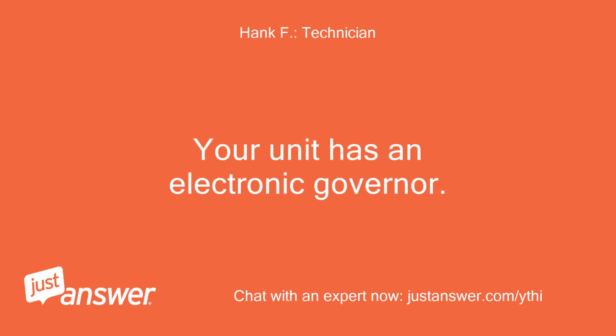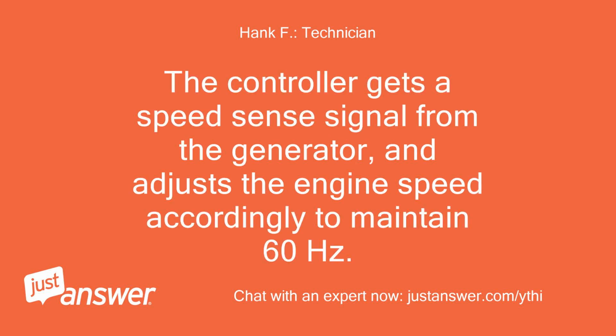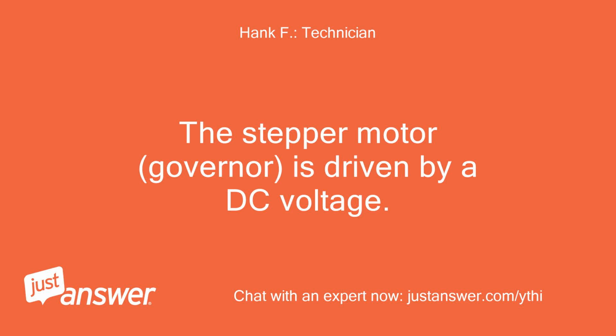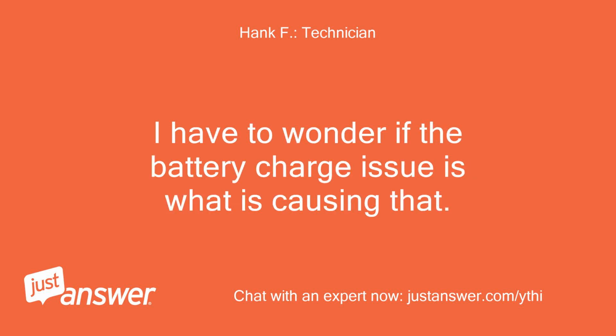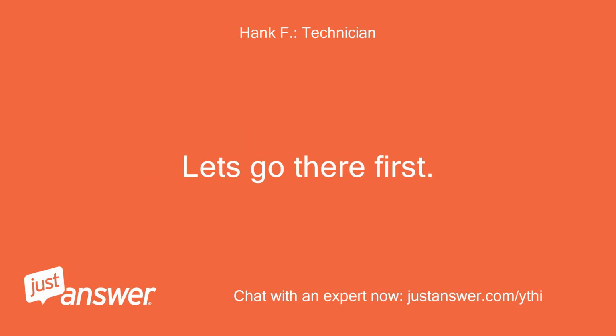Your unit has an electronic governor. The controller gets a speed sense signal from the generator and adjusts the engine speed accordingly to maintain 60 Hz. The stepper motor, governor, is driven by a DC voltage. I have to wonder if the battery charge issue is what is causing that. Let's go there first.